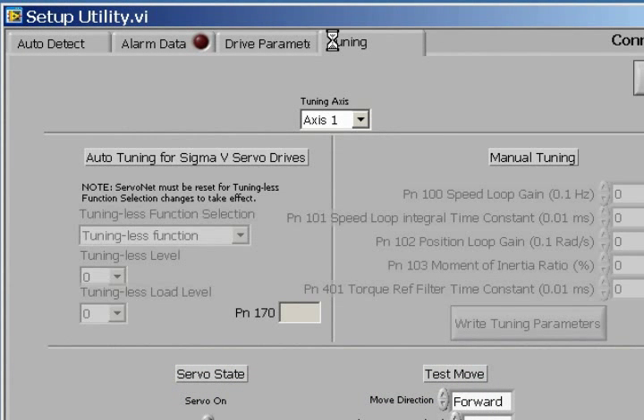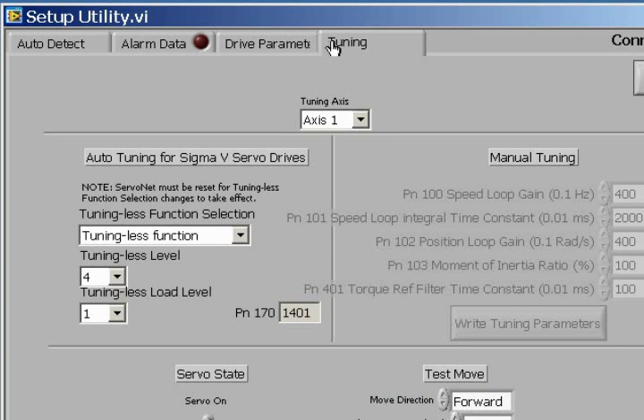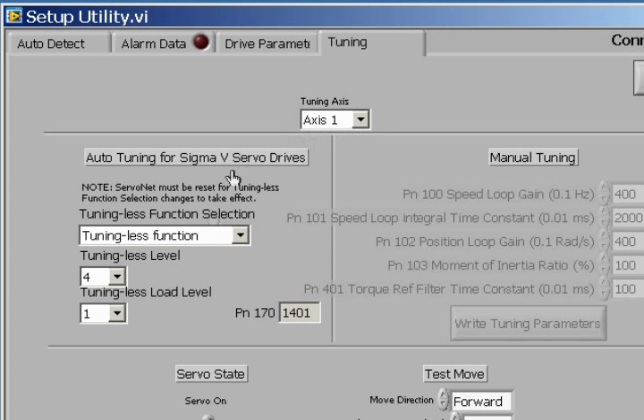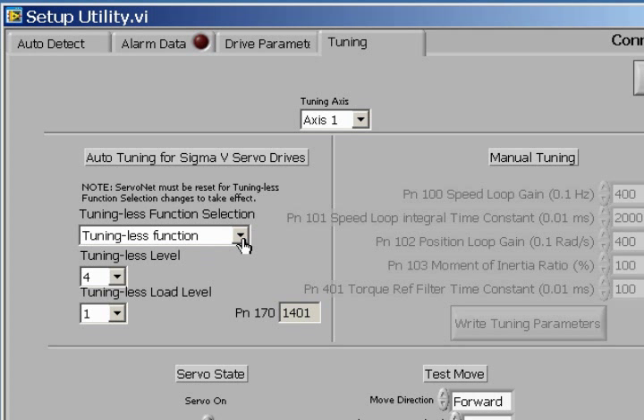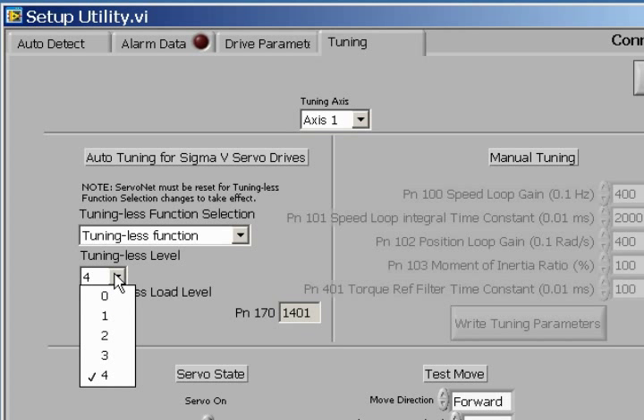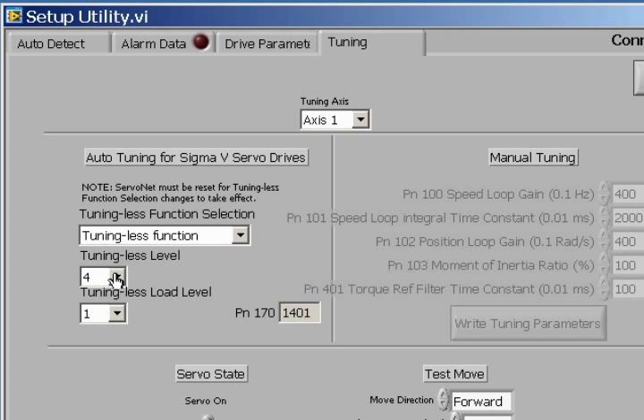Now let's click on the Tuning tab. We are connected to Axis 1. We are running the Tuning Less function enabled, which means we have enabled the real-time adaptive tuning of Sigma-5 servo drive. The Tuning Less level is set to 4, the stiffest, because we have no load connected to the motor. The load level is set to 1, since we are running in a zero load for this example.